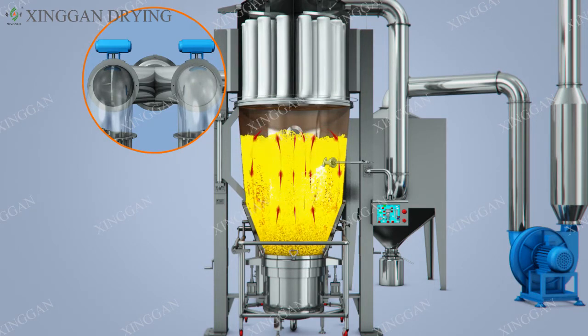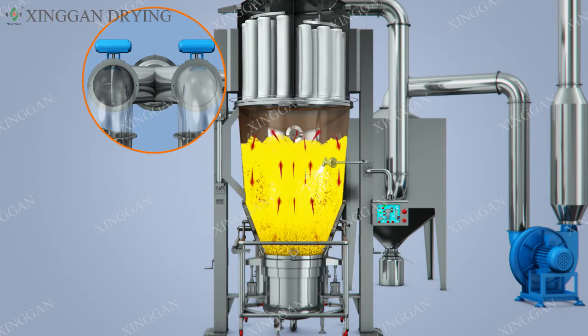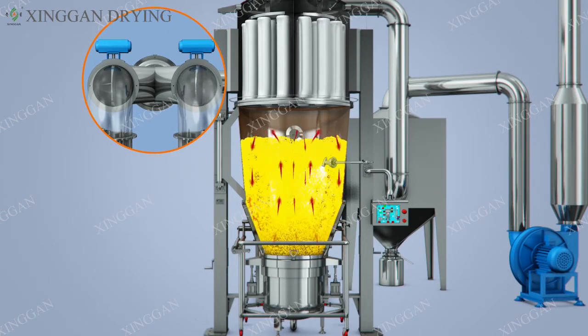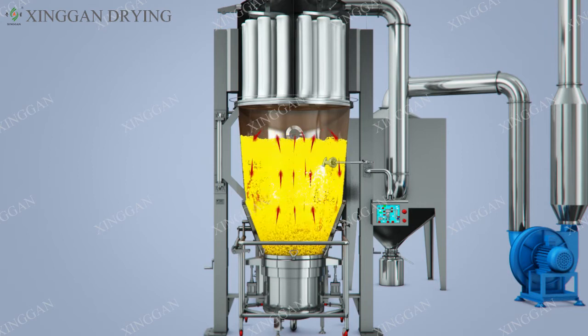The right exhaust valve closes and the right chamber filter bag of the filter chamber shakes. The left and right rooms oscillate alternately in this cycle, working continuously, clearing the collected powder, keeping the filter bags open, and efficiently completing the mixing, drying, and granulating operations.